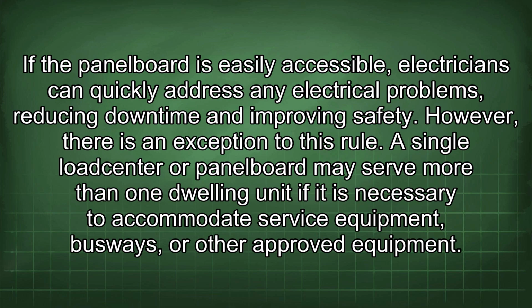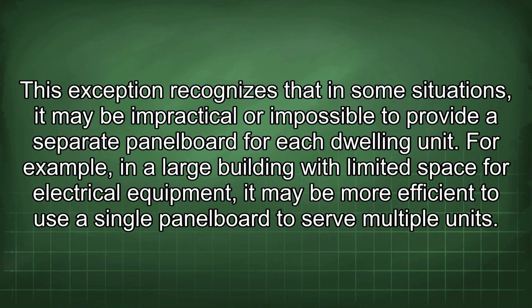However, there is an exception to this rule. A single load center or panel board may serve more than one dwelling unit if it is necessary to accommodate service equipment, busways, or other approved equipment. This exception recognizes that in some situations, it may be impractical or impossible to provide a separate panel board for each dwelling unit. For example, in a large building with limited space for electrical equipment, it may be more efficient to use a single panel board to serve multiple units.